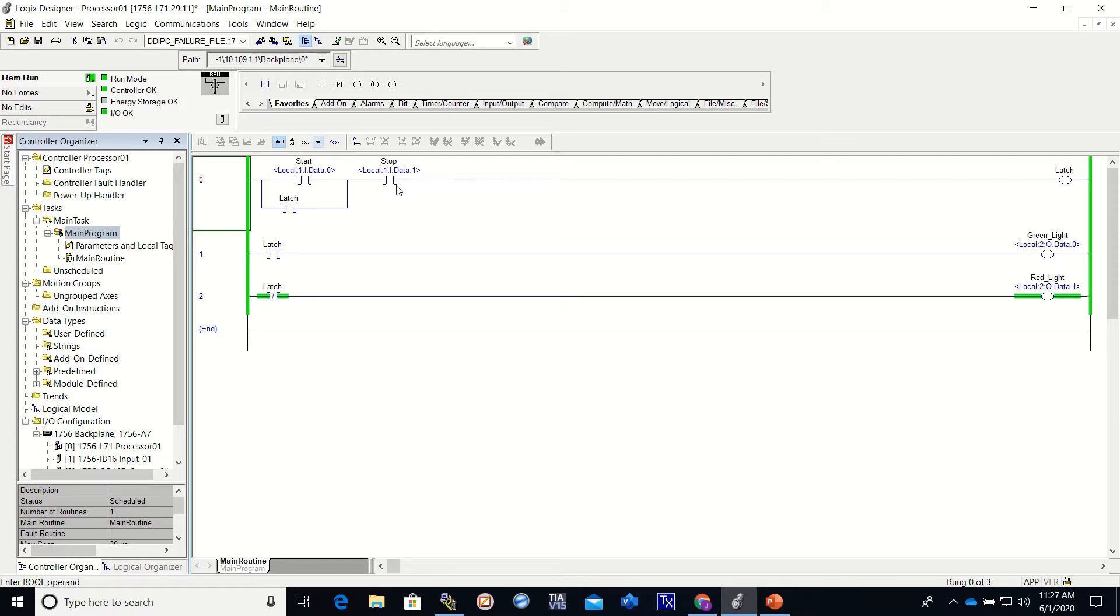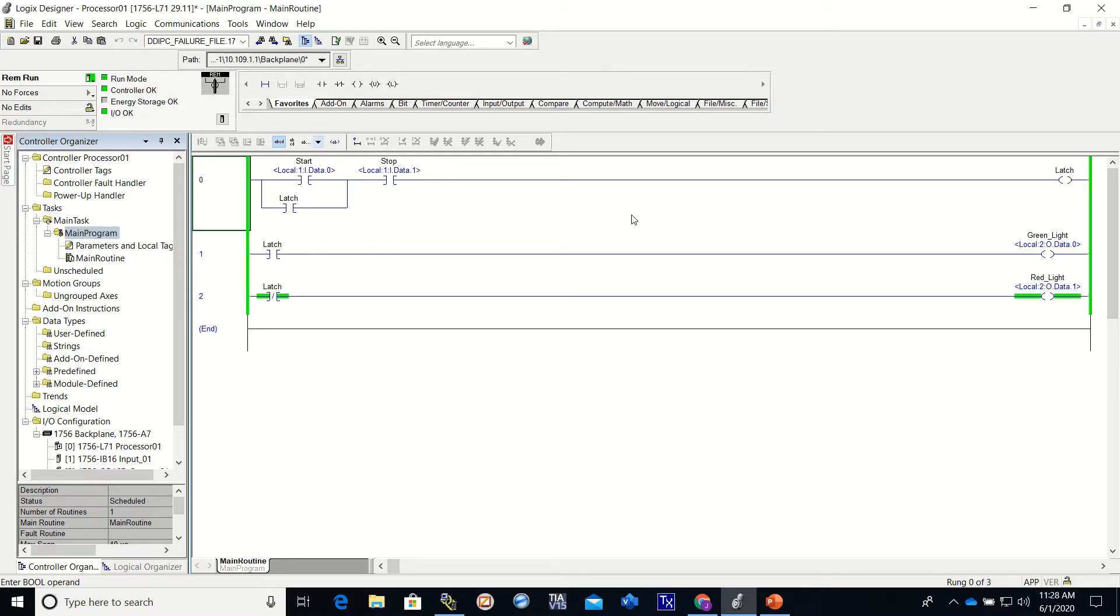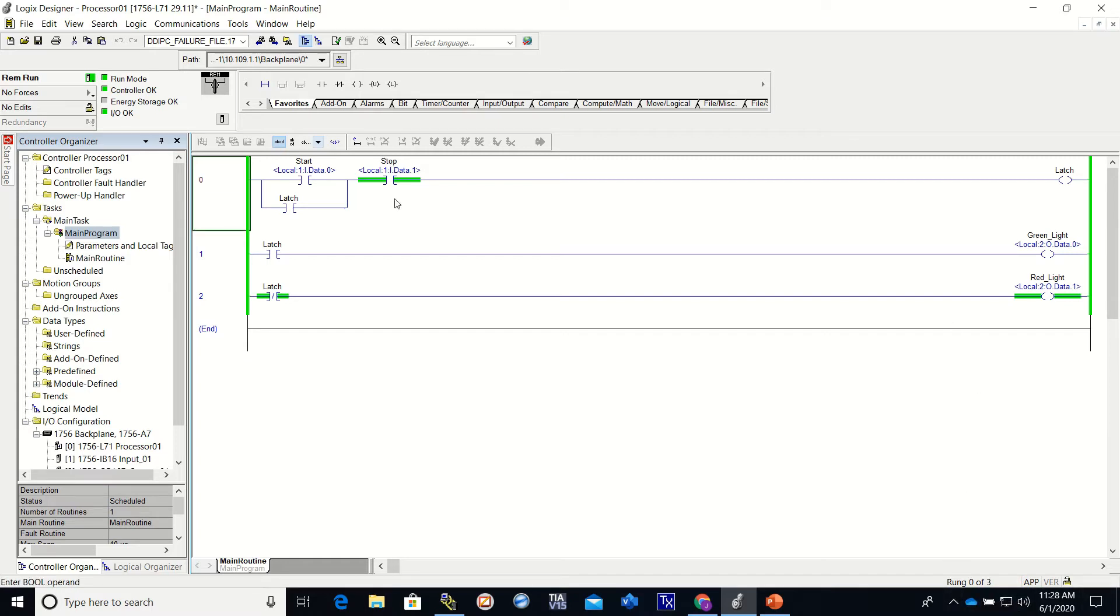Now, our start is a normally open push button, and we tied it to an examine on. Our stop is a normally closed push button, and it is tied to an examine off, and it's controlling the latch. All right, so there we go - there's our normally closed push button, which is the stop.